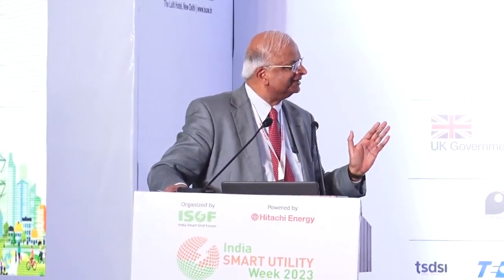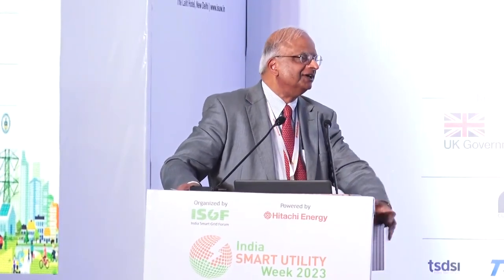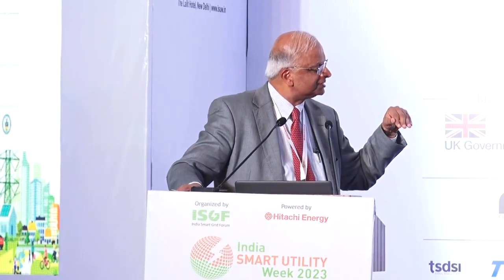Thanks. On your curve, I was interested - for countries like India, South Asia, Southeast Asia, if you were to move the axis from 40 degrees centigrade and push it to 55, 56, 60 degrees, do you think your curve will still be relatively linear, or would it suddenly become very nonlinear? This is a good question - is this curve actually linear? It will drop stronger, I'm pretty sure, but you cannot extrapolate this curve from a German wind farm transformer to an Indian transformer, because the thermal design could be different. This has to be checked. I cannot guess the situation at 50 degrees Celsius for an Indian distribution transformer from this German wind farm transformer data. That's impossible. We have to investigate that.